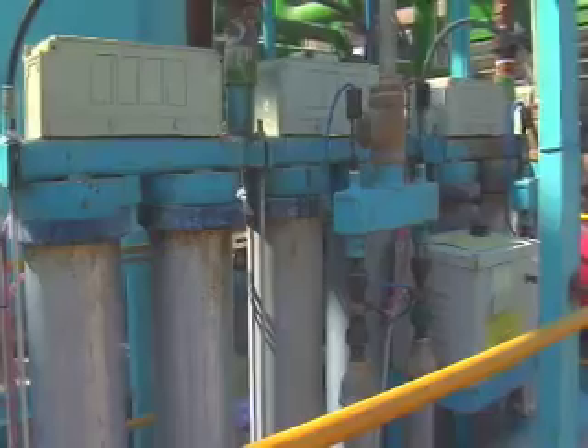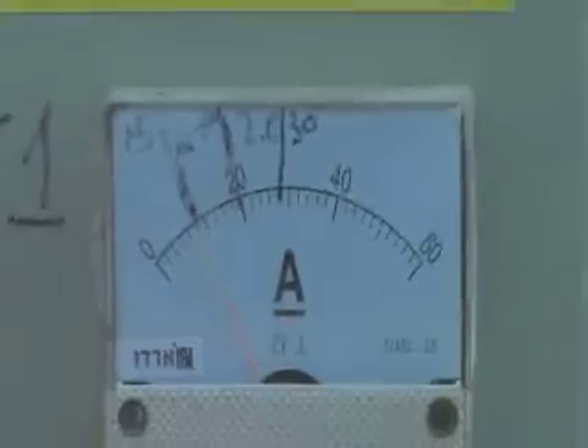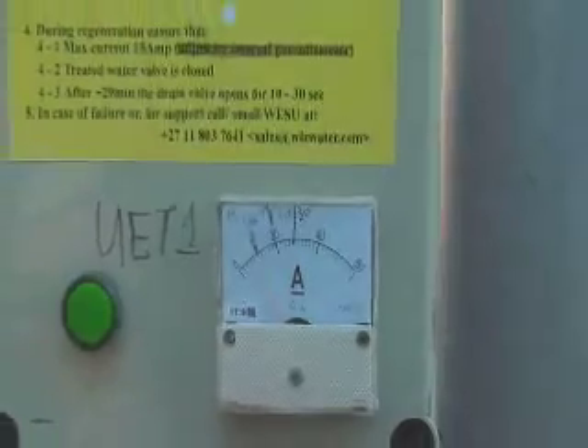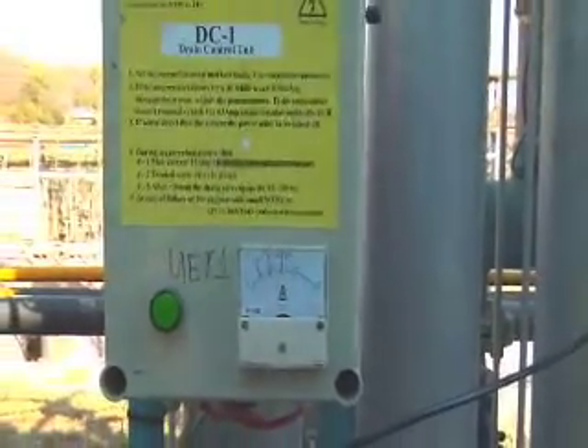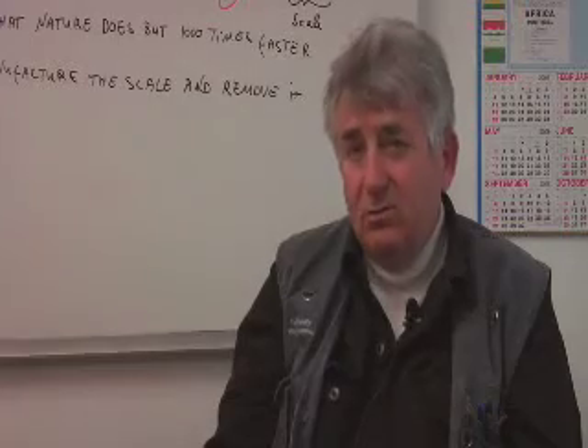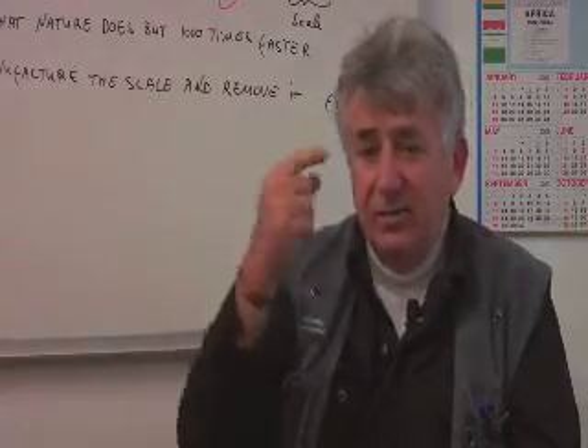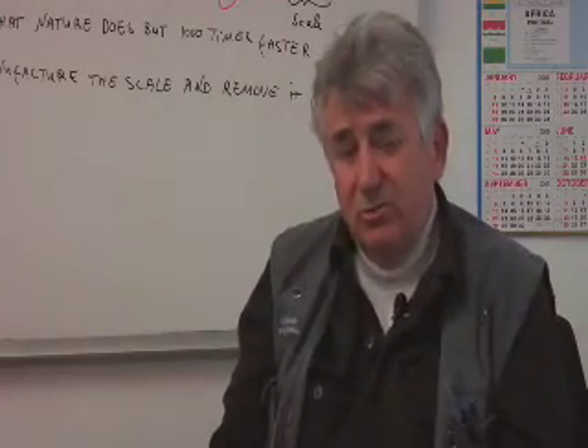It has proven itself in that the temperatures of the cooling coils show that there's no scale buildup. So we have a very high heat transfer rate through the cooling coils. There has been no detectable deterioration of the transfer rate due to scale formation in the cooling pipes. All the indications that we monitor show that it's working, and we're getting very good results from it. The amount of electricity we are using is about 200 watt per 50 cubic meter per hour, which is like the lighting in this room, or 400 watt when we are using it on a cooling tower.